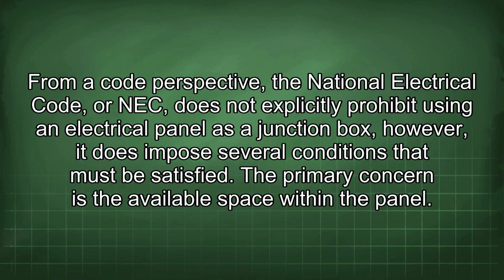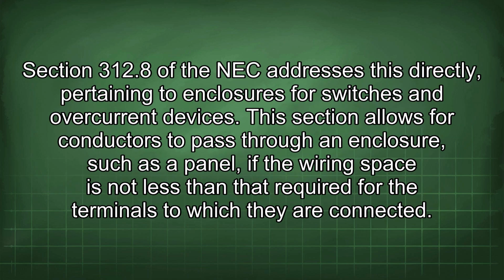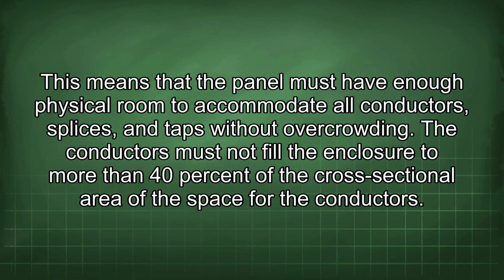From a code perspective, the National Electrical Code, or NEC, does not explicitly prohibit using an electrical panel as a junction box. However, it does impose several conditions that must be satisfied. The primary concern is the available space within the panel. Section 312.8 of the NEC addresses this directly, pertaining to enclosures for switches and overcurrent devices. This section allows for conductors to pass through an enclosure, such as a panel, if the wiring space is not less than that required for the terminals to which they are connected. This means that the panel must have enough physical room to accommodate all conductors, splices, and taps without overcrowding.